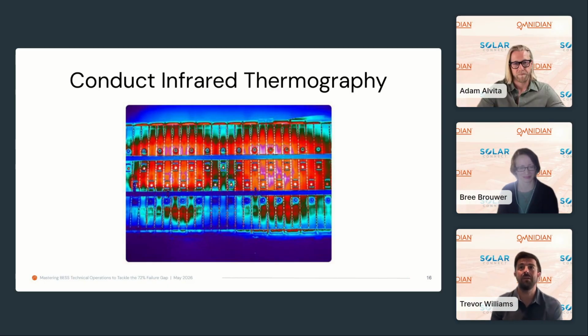Absolutely, good and bad. Because you're going to find those failures really quick with thermal imaging, and if they are that loose, you're going to have some thermal events on site. From experience, not only doing this and following through with the process, but what you see and how you correct those issues is very important. If you see something hot or a heat spike at a connection, it needs to be addressed. The torque needs to be checked, and something needs to be verified as to why it's doing that.